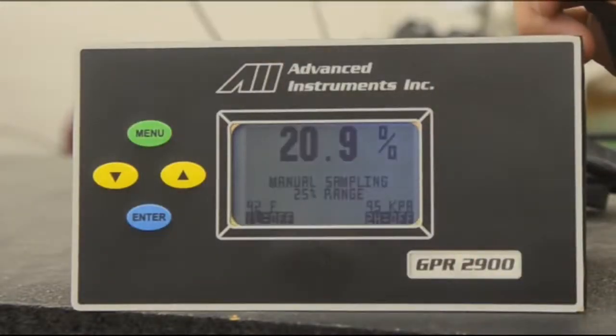After this calibration pass prompt, you'll be taken to the main menu where you will see the sensor reading at 20.9. If the sensor is bad or if the sensor is old, you will get a failed calibration prompt, and you will get kicked back to the main menu without the calibration being done. This is to prevent any faulty sensors to get calibrated to the unit.